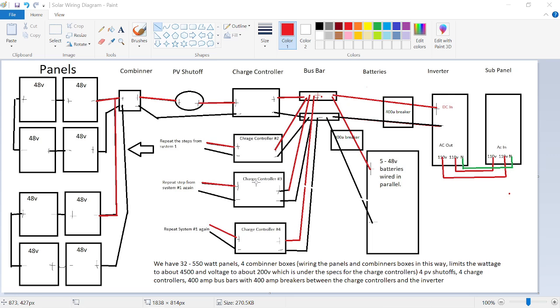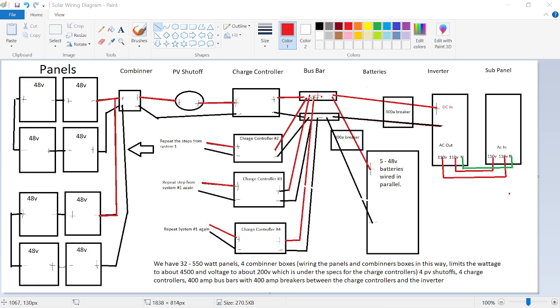So out of the charge controllers, we go to a bus bar. On the bus bar, we actually have two bus bars, two sets. There's a bus bar on the wall that everything's tied to, and then I also have bus bars on the batteries, so the batteries are tied on a bus bar on the battery rack. All the batteries tie into those bus bars, and then there's two-ought wire that goes up to the 400-amp breaker. So all the charge controllers tie into the two bus bars, all the hots on one, all the colds on the other.